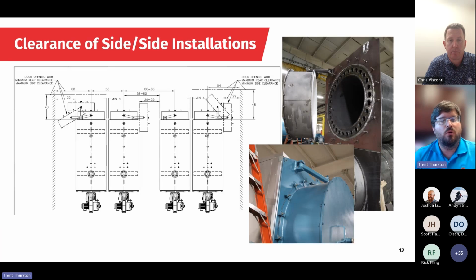So what this allows us to do is put pairs of boilers as little as 4 inches apart. Now, each pair of boilers will need a maintenance corridor on each side to allow space for the door to swing and, again, for maintenance and inspection. We do show 2 different ways of door swing clearance. On the left there, the door is opened first and then rotated on the pin at the very end. Opening it this way gives the minimum rear clearance in case there's an issue with clearance at the back. On the right side, we start rotating on the pin as soon as possible, which gives us the minimum side clearance if that's what's required. Yes, this door will spin both on the davit and also on the pin.